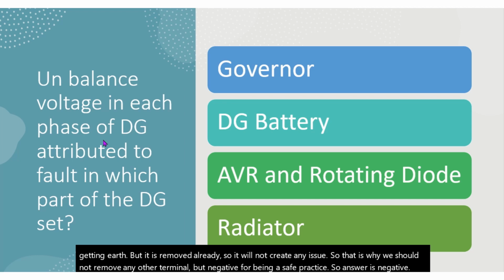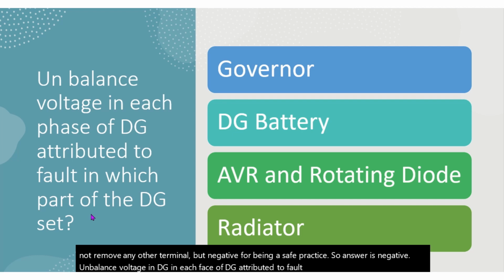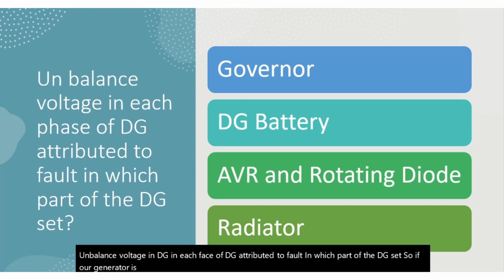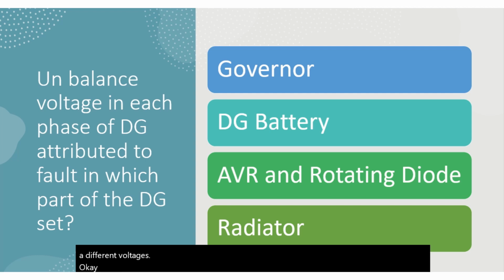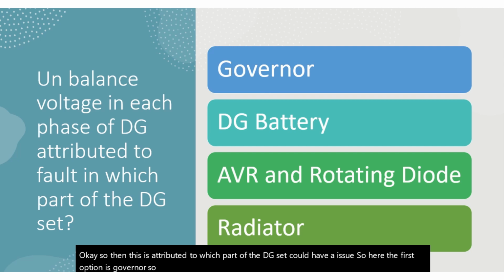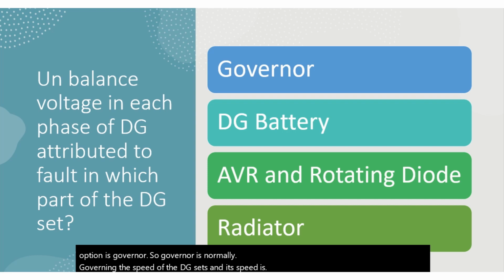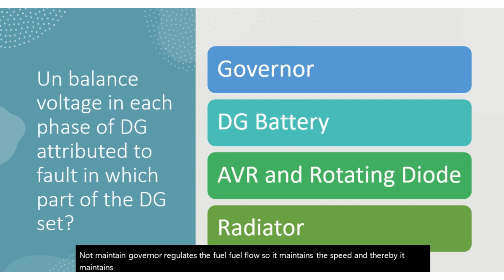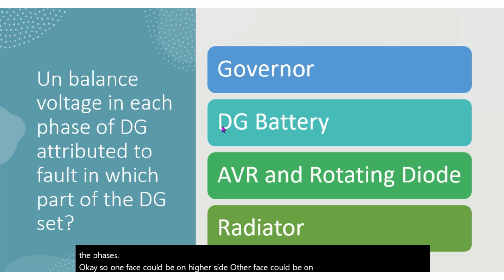Unbalanced voltage in each phase of DG is attributed to a fault in which part of the DG set? If our generator is running but we are not getting a proper voltage in any phase, and every phase has a different voltage, which part of the DG set could have an issue? The first option is governor. The governor governs the speed of the DG set, and if speed is not maintained, the governor regulates the fuel flow. So it maintains the speed and thereby the frequency. Yes, a higher frequency creates a higher voltage, but it will create a higher voltage in every phase. Here we are talking about unbalance among the phases. One phase could be on the higher side, another on the lower side. So governor is not the answer.